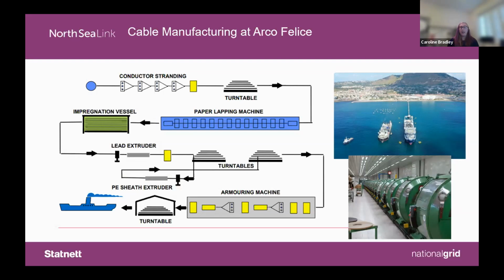To make a mass impregnated cable, there are multiple steps. You strand the conductor, then lap the paper on, then impregnate it with oil. There are more steps to extrude the metal and polyethylene sheaths onto it for protection, and then you armor it. If the cable isn't being used offshore, you skip the armor stage and go straight to delivery, but otherwise the cables are the same.